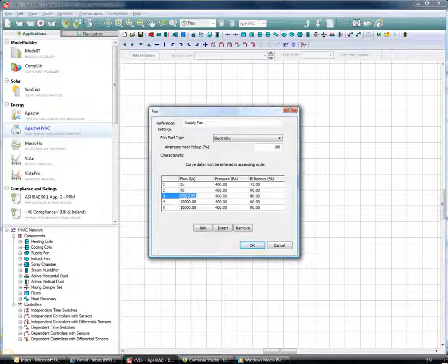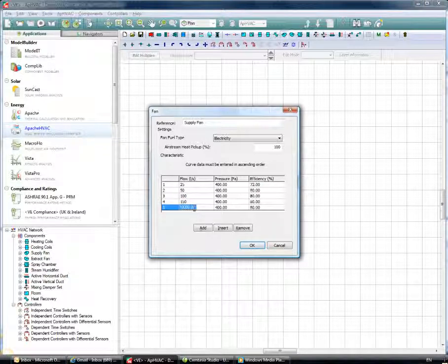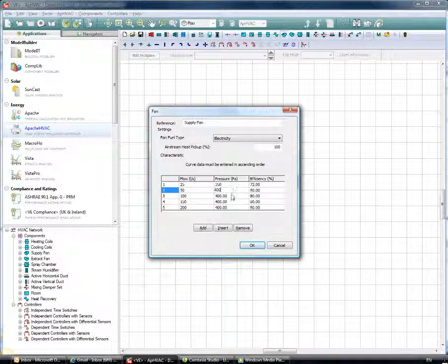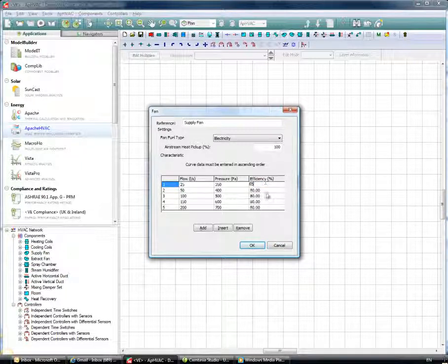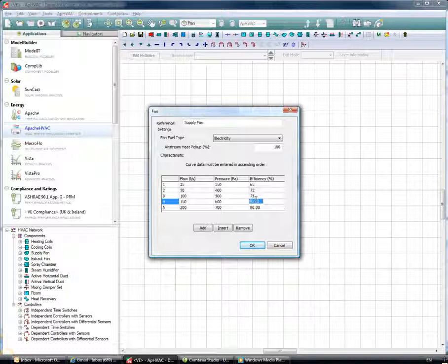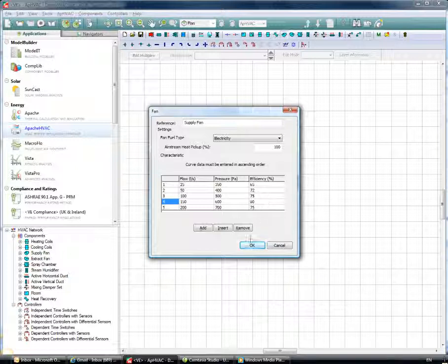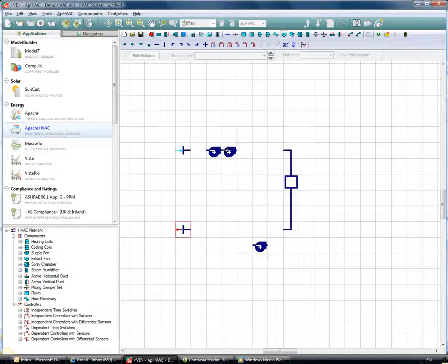An important point about this fan: it is not controlling the flow rate in the system — it's acting like a meter, metering the flow rate passing through it. Based on that flow rate and the pressure, efficiency, and flow rate figures entered in the curve, it will predict the power consumption and energy the fan will be consuming at that point on the curve. It's more of a metering device allowing us to predict energy consumption. We can control flow rate in a different way using flow controllers. Clicking OK, the supply fan is in place.